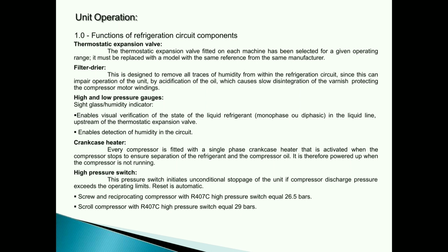Unit operation. 1.0. Functions of refrigeration circuit components. Thermostatic expansion valve. The thermostatic expansion valve fitted on each machine has been selected for a given operating range. It must be replaced with a model with the same reference from the same manufacturer. Filter dryer. This is designed to remove all traces of humidity from within the refrigeration circuit, since this can impair operation of the unit by acidification of the oil, which causes slow disintegration of the varnish protecting the compressor motor windings.